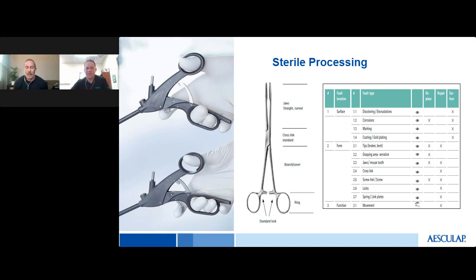He says, I must share the importance of paying attention to quality of our instruments during the decontamination process is paramount. I came across a Cobb elevator, which I would never have known the handle was hollow. Upon placing my instruments in my sink shortly afterwards, I noticed a steady stream of bubbles coming from the handle of the Cobb elevator. It was an exciting find and a scary find. To think that this was a pinhole on the handle allowing for fluid invasion. Imagine the gross contaminants contained within.